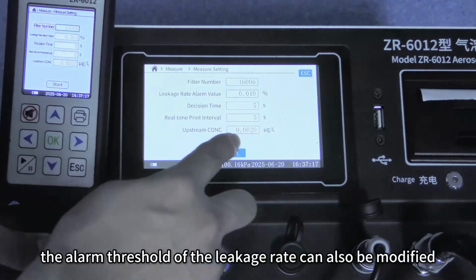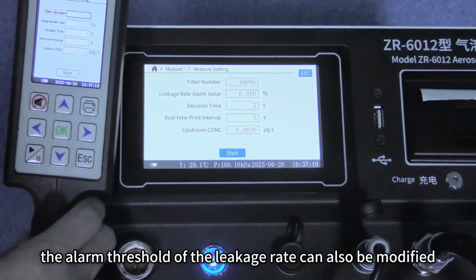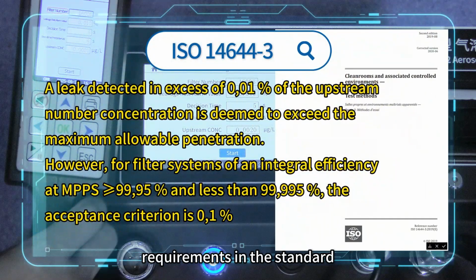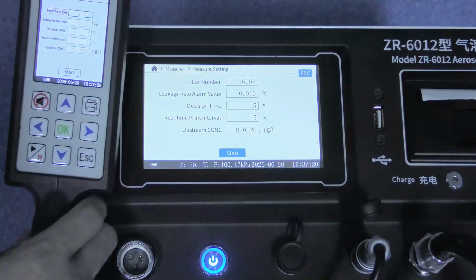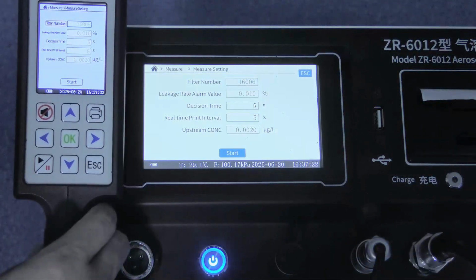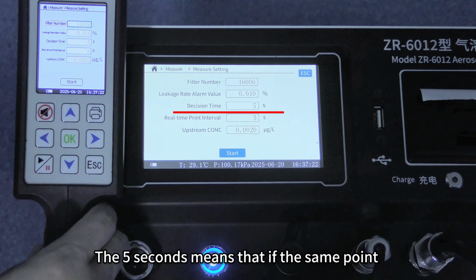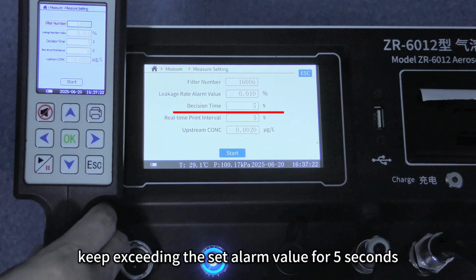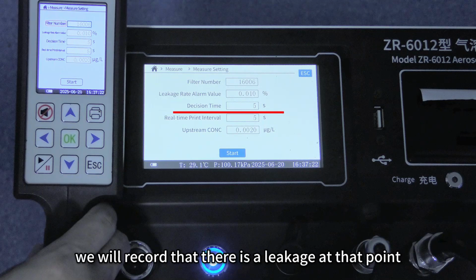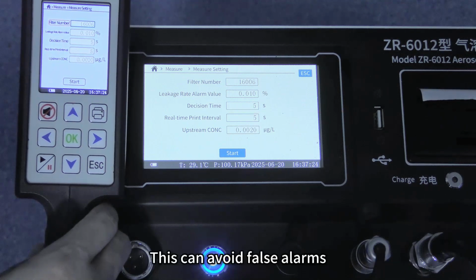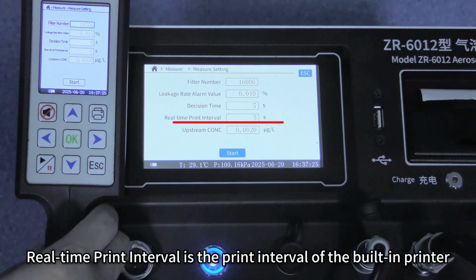The alarm threshold of the leakage rate can also be modified. You can set leakage rate alarm value according to the requirements in the standard. The decision time can be set. The 5 seconds means that if the same point keeps exceeding the set alarm value for 5 seconds, we will record that there is a leakage at that point. This can avoid false alarms. Real-time print interval is the print interval of the built-in printer.